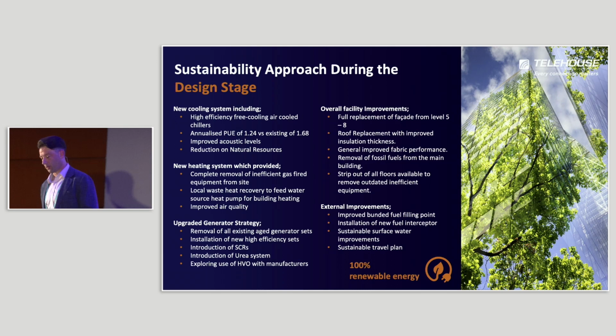We had 30-year-old generator sets in the building that were very, very uneconomical. A lot of carbon was coming from those, and a lot of NOx levels put into the local area. We've completely revised that. All of the old generation is removed from site or about to be removed from site. We have a new generator being installed at the moment and under testing. Highly efficient generator sets, so they're 2G generator sets from Rolls-Royce. New SCRs, so catalytic converter reduction, 90% reduced nitrous oxide into the area. Urea system, which is AdBlue for a normal car user.